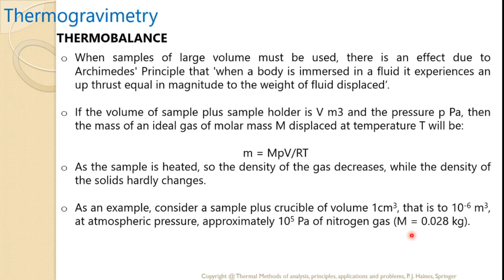If the volume of the sample plus sample holder is V meter cube and the pressure is P Pascal, then the mass of the ideal gas of molar mass M displaced at temperature T will be given by m = MPV/RT. As the sample is heated, the density of the gas decreases while the density of the solid hardly changes. As an example, consider a sample plus crucible of volume 1 cubic centimeter, that is 10 raised to minus 6 meter cube, at atmospheric pressure, approximately 10 raised to 5 Pascal, of nitrogen gas.